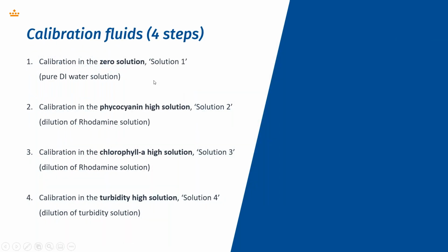The calibration with the fluids goes in 4 steps. I've mentioned the steps here in general, but in the manual, all the steps are described in detail. So from the manual, it is easy to do the calibrations. I said 4 steps. The first step is calibration in the zero solution, called solution 1. It's a pure deionized water solution, and it is used to set up the 0 point.